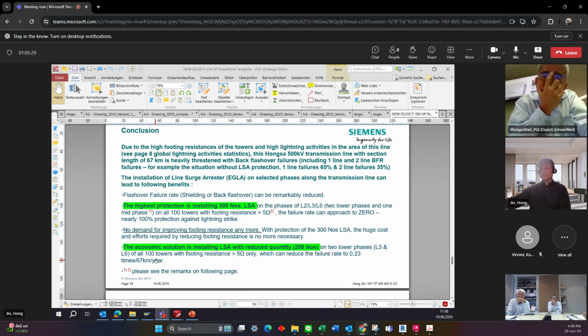The economic solution is to install lightning arresters, only 2 units per tower, for the towers that have ground resistance more than 5 ohm. Yes. And the tripping rate is 0.23. This is a different result from the simulation: one time per 100 kilometers per year. Yes, we recommend this.